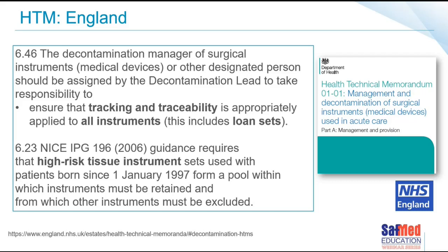In the South African setting, we have already had incidences of patients diagnosed with Creutzfeldt-Jakob disease — this has been presented at our CSSD Africa Health Congress. If a patient is diagnosed with CJD, how are we going to identify exactly which set was used on them, and subsequently — because you may only find out weeks later — which other patients that same set was used on? Those patients are at great risk.